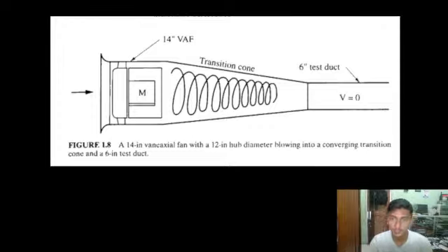After the designer put two longitudinal cross sheets in the transition cone to prevent the air spin, the proper airflow was restored and a fairly normal duct test could be run. That's the illustration I just found.